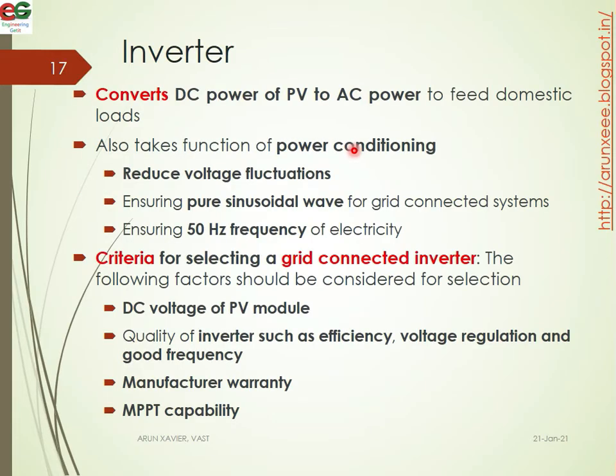Inverters convert the DC power of the PV system to AC power for domestic loads. They also perform power conditioning, which manages voltage fluctuations and ensures a sinusoidal wave at 50 Hz frequency. For selecting a grid-connected inverter, the following factors should be considered: DC voltage of the PV module, inverter efficiency and voltage regulation, frequency, and the manufacturer's warranty.